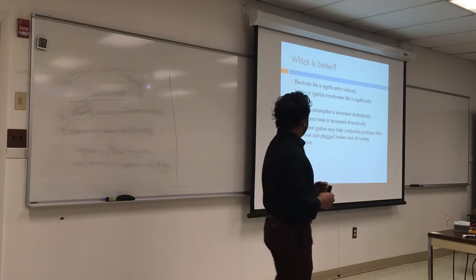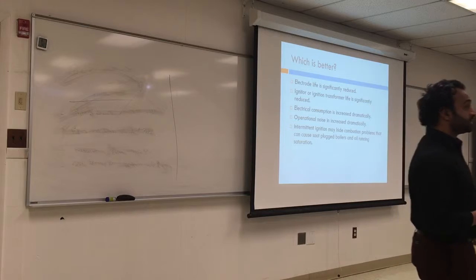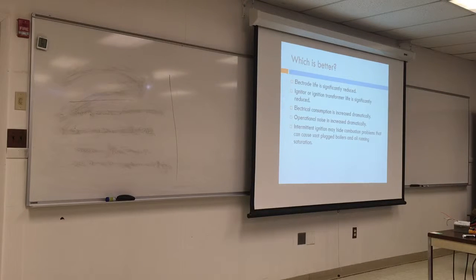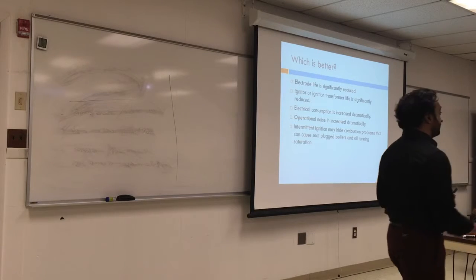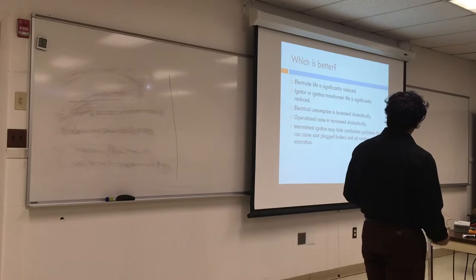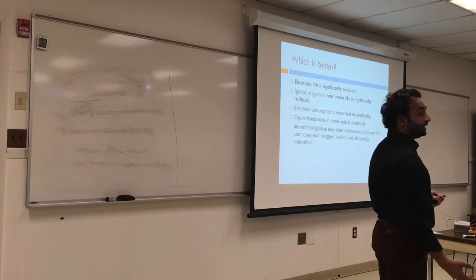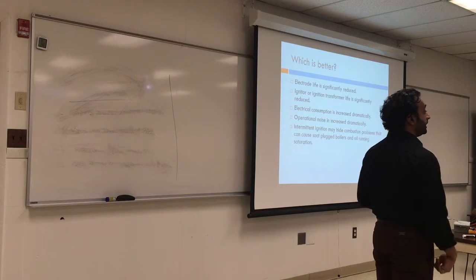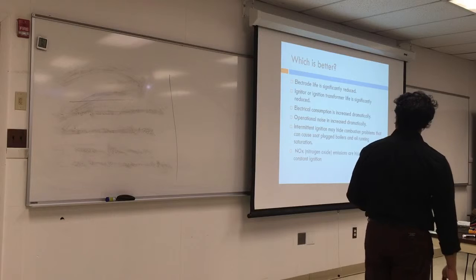Intermittent ignition may hide combustion problems that could cause soot and plug boilers. If you are burning rich or lean, or you have a lot of smoke, you're still going to run, even though it's not with a proper fire, and that will lead you to not know about this problem. Eventually, it will clog your chimney, and you need to have the boiler serviced. So it causes a lot of problems, and you don't know if you're getting good combustion or not. And again, it will add to your cost of fuel operation.